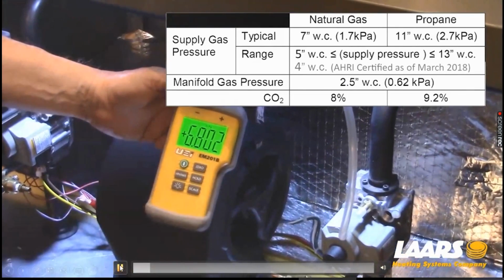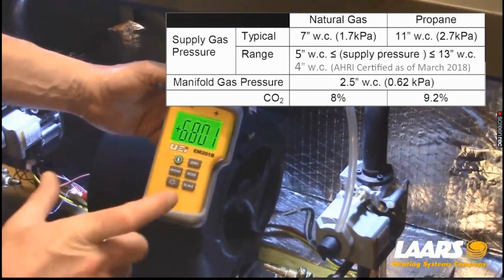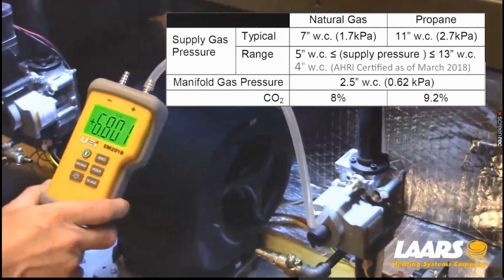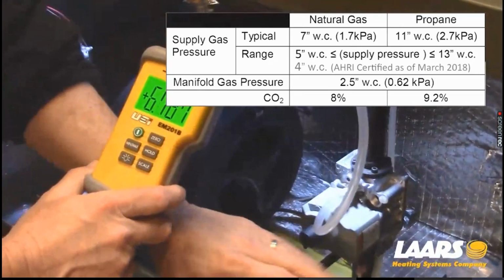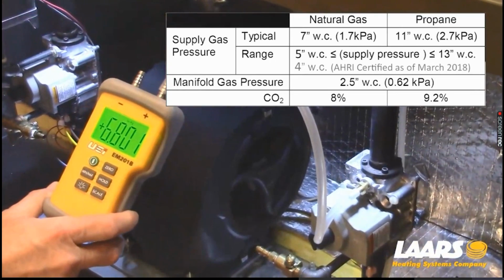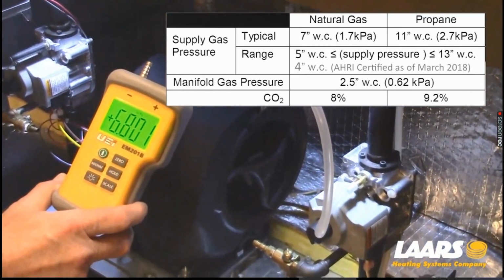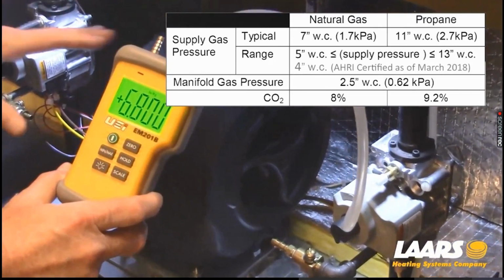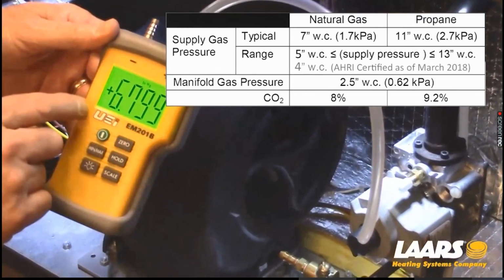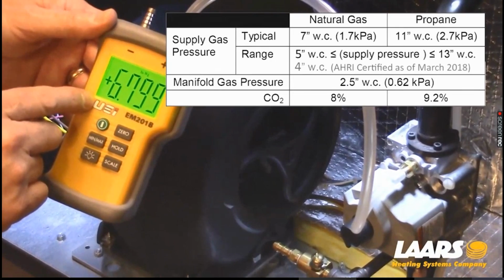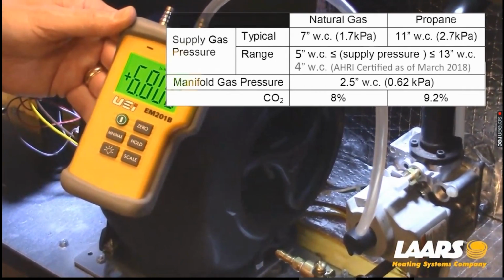So at 6.80 inches of water column, that should be static gas pressure. None of my valves are on the boiler. Static is the gas pressure sitting idle. We also want to run another test when we're done with all valves running to make sure that this gas pressure does not drop below 5-inch minimum.